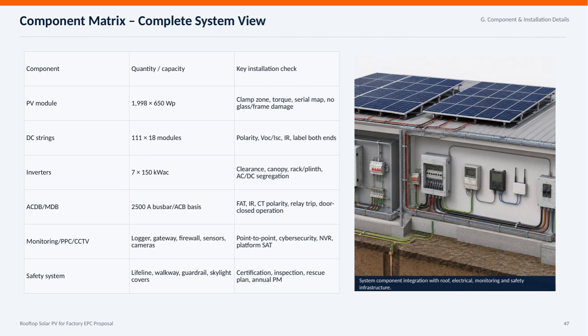The AC distribution boards are designed for a 2,500 amp bus bar, with rigorous testing like factory acceptance tests and relay trip verifications to ensure reliability. For monitoring and control, we integrate loggers, gateways, firewalls, and sensors, supported by CCTV to provide thorough oversight, with cybersecurity measures and platform acceptance tests in place. Lastly, the safety system incorporates lifelines, walkways, guardrails, and skylight covers, all certified and inspected regularly with a rescue plan and preventive maintenance program. Altogether, these components are meticulously integrated with the roof, electrical, monitoring, and safety infrastructure to deliver a robust and secure solar power installation.